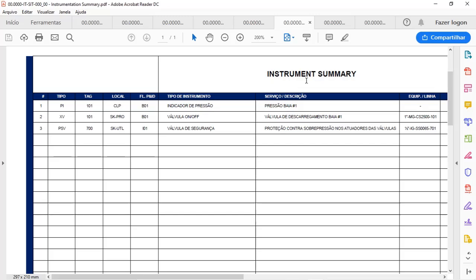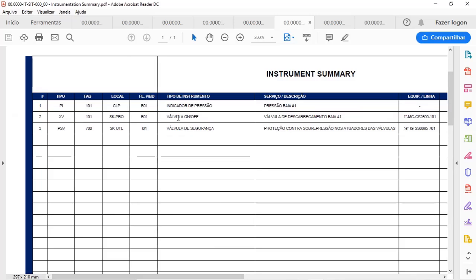Here you can see that I have, for instance, a pressure indicator with the tag of this instrument and the location where its information will be sent. We have also an automatic valve that is just on-off, not for control but only for blocking. And I have also here a pressure relief device, in this case a pressure safety valve with its tag and location.